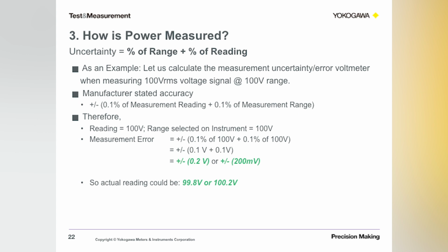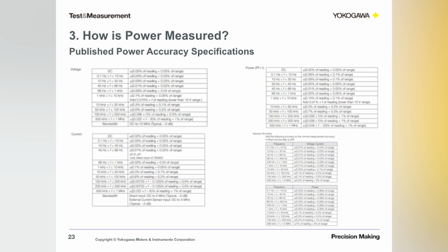Many manufacturers will only state the reading error, and you can see that you have to account for the range error as well, because your actual error is slightly larger than just your reading error. So when you're looking at a power measuring device, make sure that you look for these stated uncertainties, not only for voltage and current, but also for power. If you're measuring harmonics, then the device should also state accuracies or inaccuracies for the harmonics as well. Since you're measuring power and that's what the device is purpose-built for, you definitely should look for the power uncertainties that are provided there. Okay.